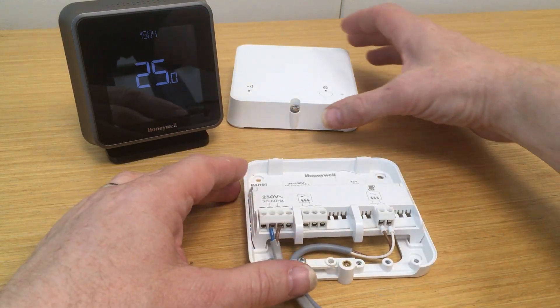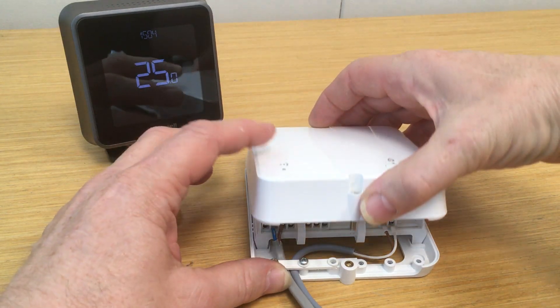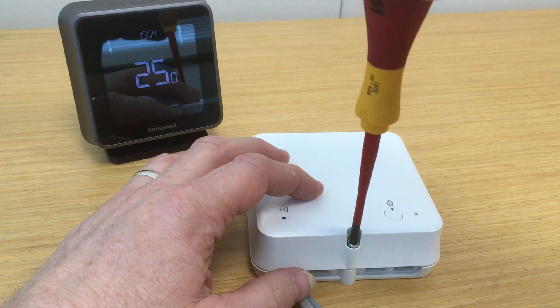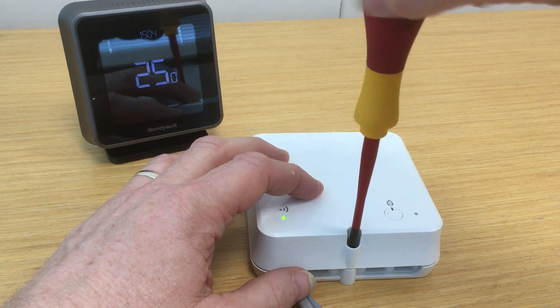Note that when using the T6 in OpenTherm mode, the normal switch live or switched connections become disabled — they are no longer usable once you make the connection to the OpenTherm terminals. So that's the wiring on the base plate. We'll replace the relay box electronics module like so, and secure the retaining screw like so.